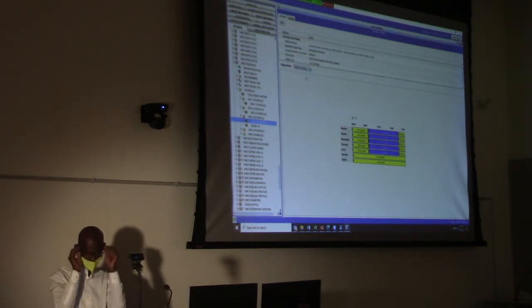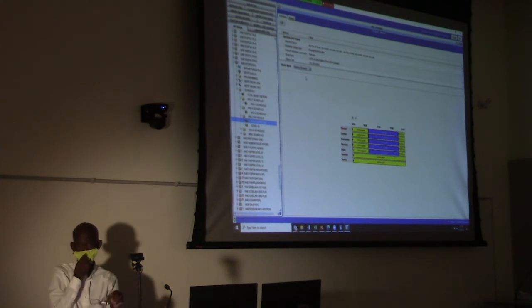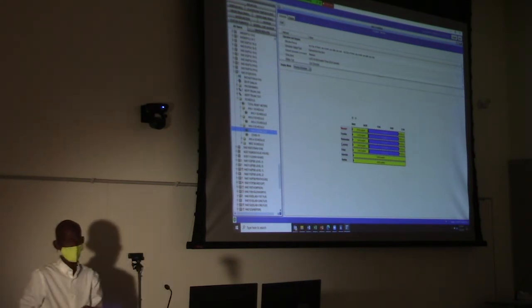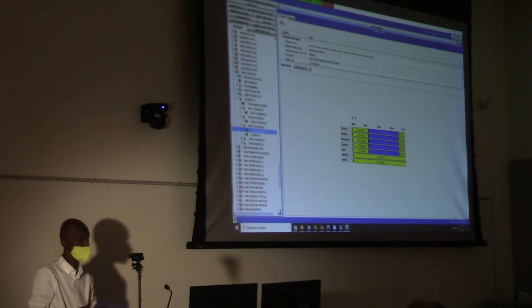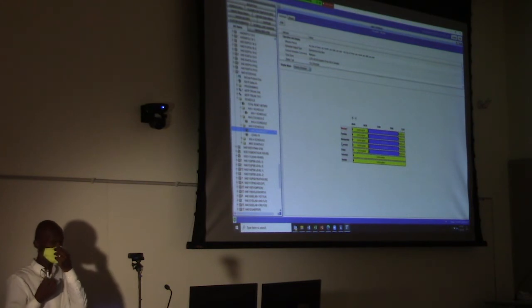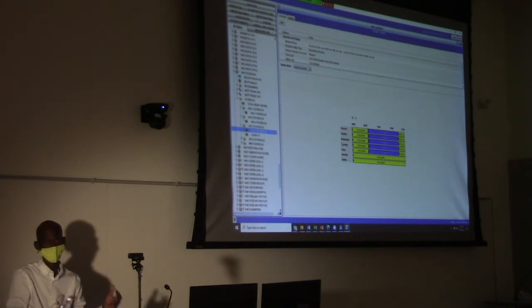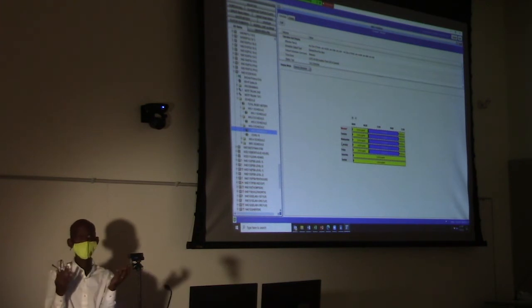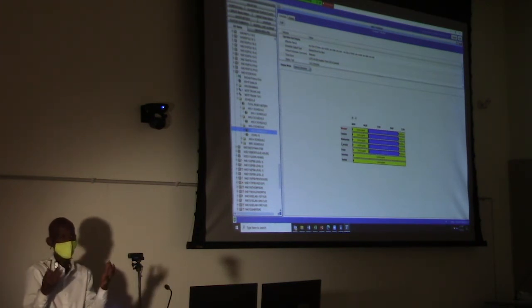HU3, which serves the main entrance, runs 6 a.m. to 9 p.m., Monday through Friday. So this explains why you have those spikes, because you have all the equipment starting at 6. You go from, let's say, 62 degrees. You want the room to come to 70 degrees before students walk in at 8 o'clock. Guess what? You're going to have that high demand of steam, so that you can heat your building.